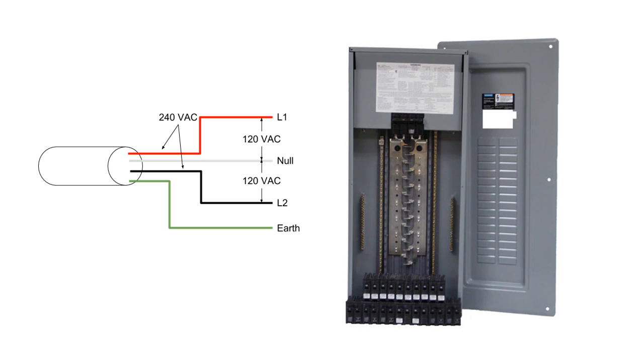You would think that if we consume 1 kilowatt of energy, and if our special inverter pumps an equal 1 kilowatt of energy into the panel, then the energy supplied from the grid would be zero. Except in the case where the left and right sides consume a different amount. If the right loads consume 800 watts and the left consumes 200, some of the current will flow in the null wire to the transformer and back down to the right side of the panel.